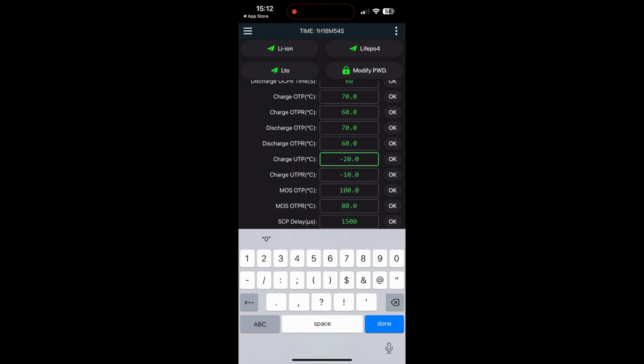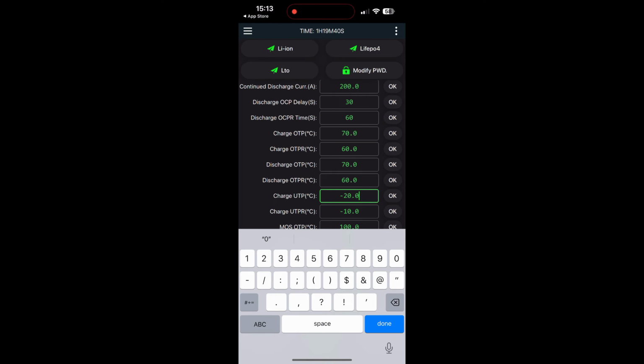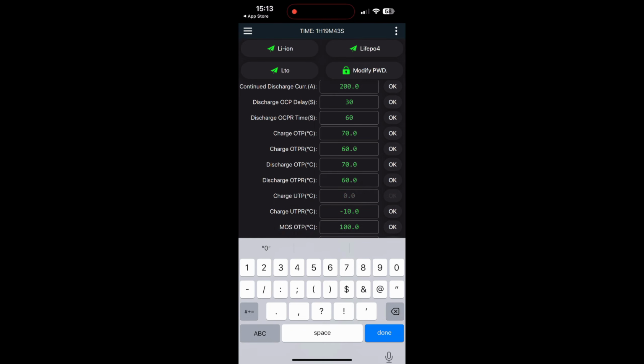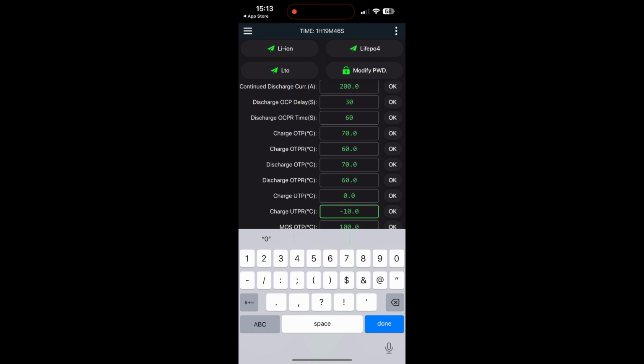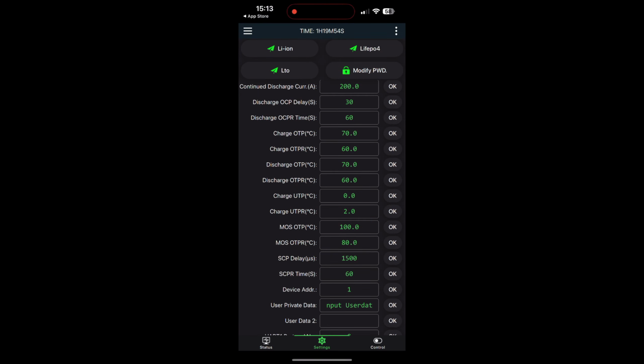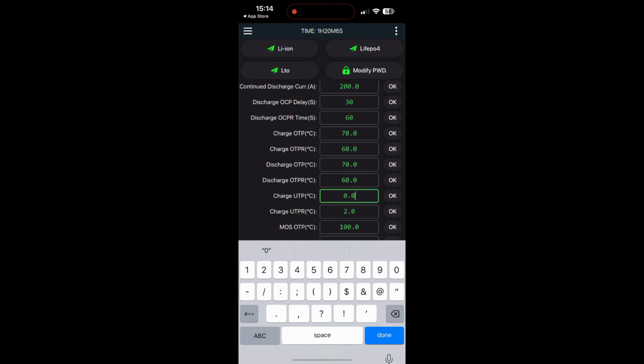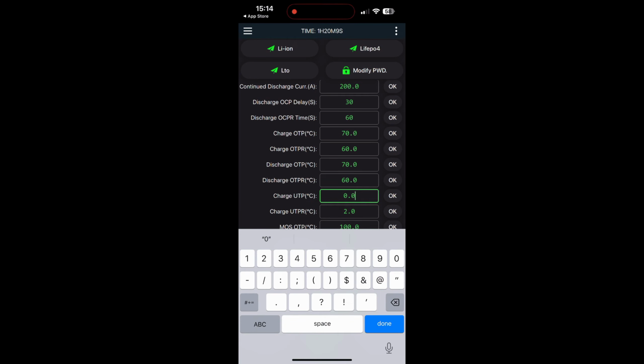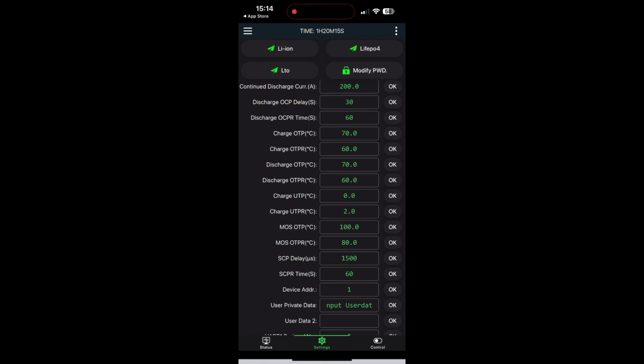Okay. Charge under temperature protect. You really shouldn't be charging these cells below zero. So for this setting, under temperature protect, I'll change that to 0 degrees, because of this setting here. So where do we want it to restart? In this instance, it'll allow the temperature of the BMS or the cells to come down to 0 degrees. It won't allow any charge to happen when it's at 0 degrees or below. However, once it's back up to 2 degrees, it will allow charge to start going back into the cells.